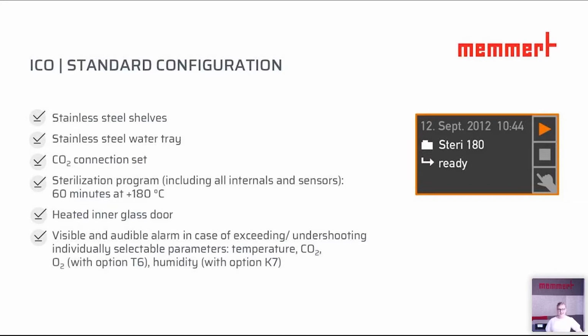connection set. But not only that, Memmert also provides a very handy, very convenient, and pre-installed sterilization program, which runs for 60 minutes at plus 180 degrees Celsius. Important to note here is that, first of all, it is a sterilization program, not a decontamination cycle or similar as other competitors might offer, but really hot air sterilization. And secondly, Memmert only uses such high quality products. You do not have to remove anything, any sensors or any internals before starting your sterilization. So everything can stay inside, making up for a very quick and easy sterilization cycle.